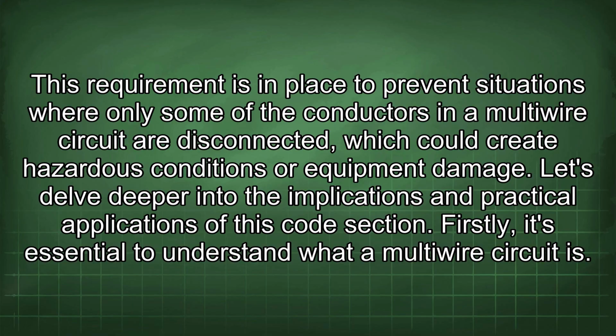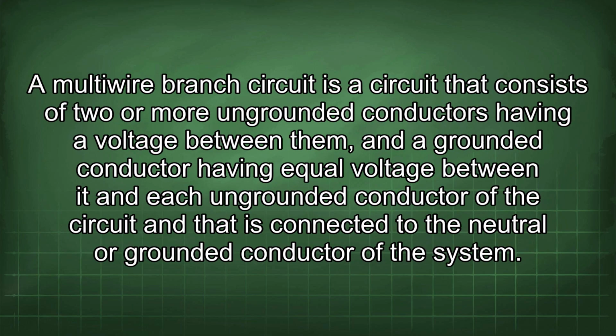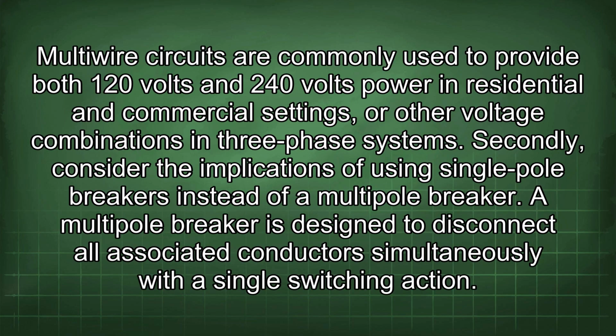Let's delve deeper into the implications and practical applications of this code section. Firstly, it's essential to understand what a multi-wire circuit is. A multi-wire branch circuit is a circuit that consists of two or more ungrounded conductors having a voltage between them, and a grounded conductor having equal voltage between it and each ungrounded conductor of the circuit, and that is connected to the neutral or grounded conductor of the system. Multi-wire circuits are commonly used to provide both 120 volts and 240 volts power in residential and commercial settings, or other voltage combinations in 3-phase systems.